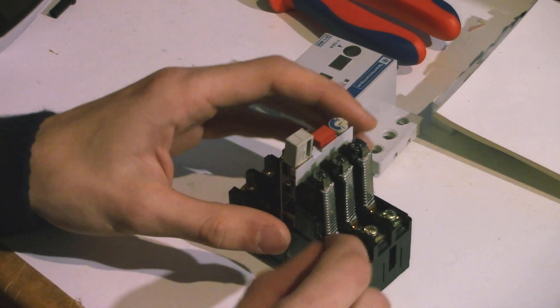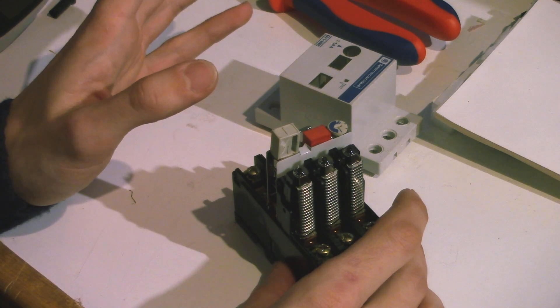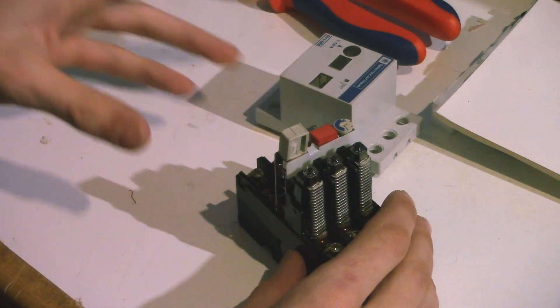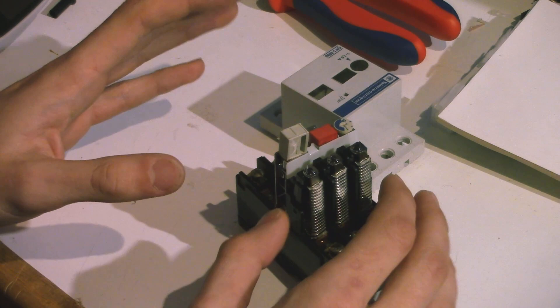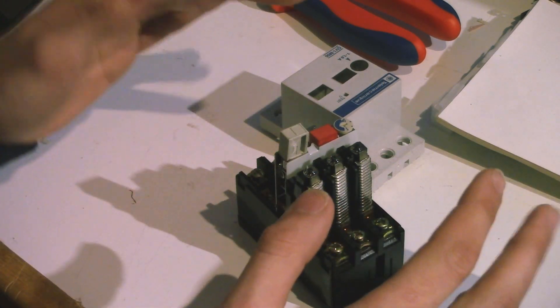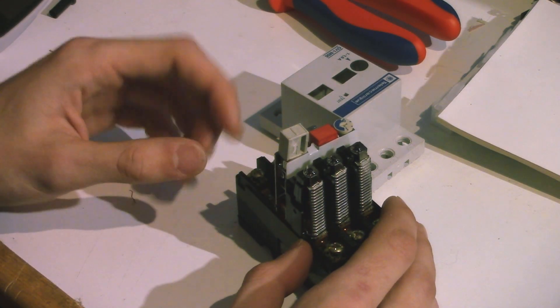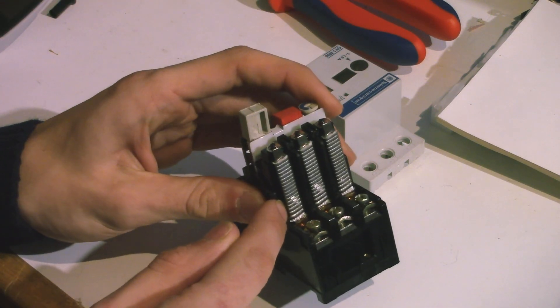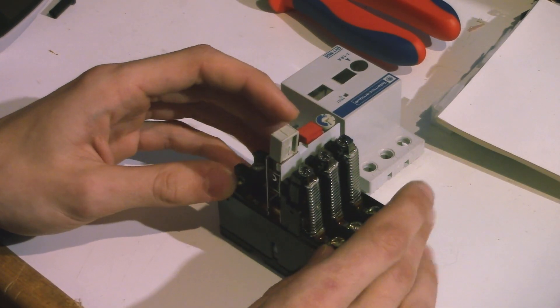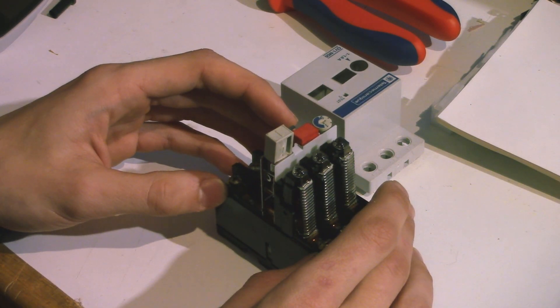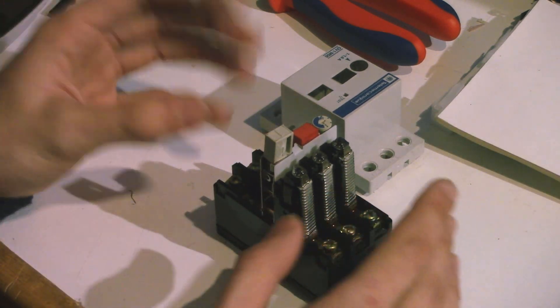And so what we have, the combined protection mechanism, is we have these bimetallic strips, the thermal protection, preventing small overcurrents, just too much current being drawn by the motor or by some appliances, slightly over the threshold. It takes slightly longer to activate, but it's probably fine because the system will handle a slight overcurrent for a small amount of time. And then for short circuits, we have an extremely fast protection mechanism, which is the magnetic protection. And so those two mechanisms are combined in a breaker switch to make sure that your house does not catch fire when there is a short circuit or when you're drawing too much current using your devices and appliances.